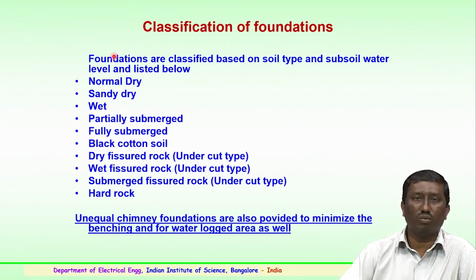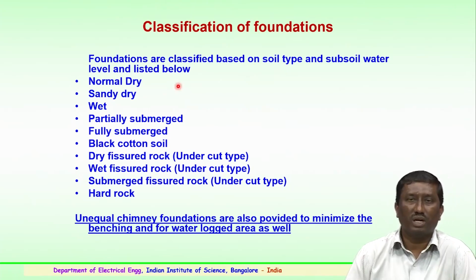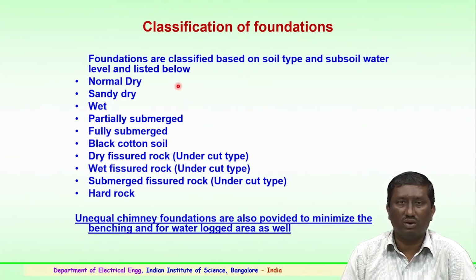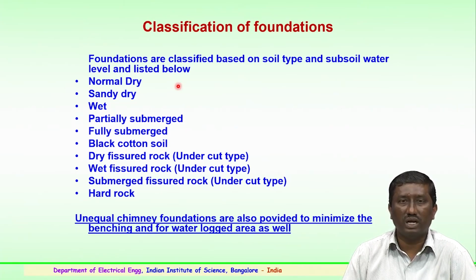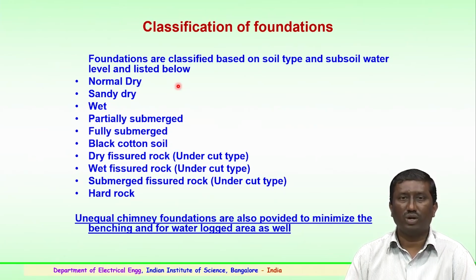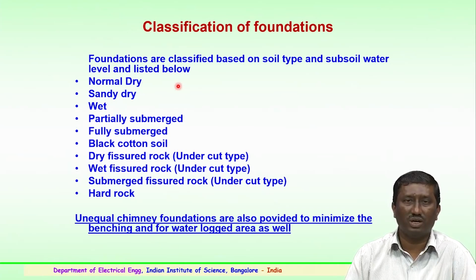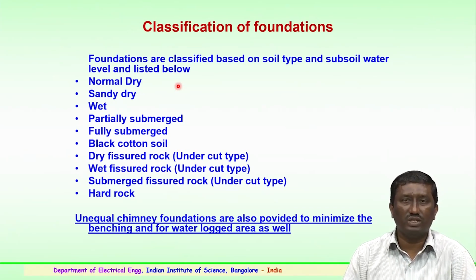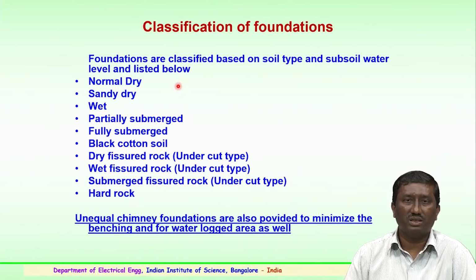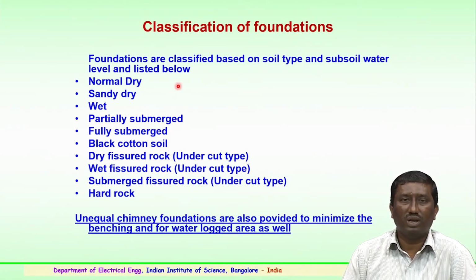So, in case of a normal dry condition of the soil, what type of foundation is to be carried out? In case it is sandy and dry, what type of foundation has to be made for the tower? Again, the tower foundations depend on the voltage level, the height of the tower, total steel structure, total mechanical load, wind consideration, insulators and conductors. So both mechanical and electrical clearances, and also civil engineering, play a dominant role for the transmission system. So the foundation is a very important aspect.